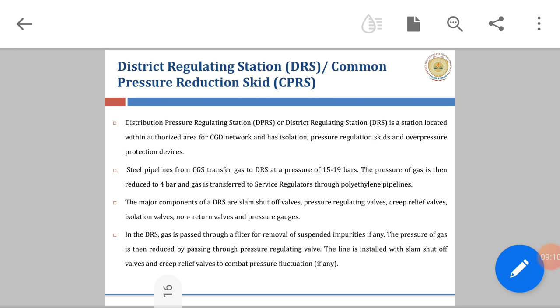The major components of a DRS are slam shut-off valves, pressure regulating valves, creep relief valve, isolation valve, non-return valve, and pressure gauges. In the DRS, gas is passed through a filter for removal of suspended impurities, if any. The pressure of gas is then reduced by passing through pressure reduction valves. The line is installed with slam shut-off valve and creep relief valves to counter pressure fluctuation, if any.